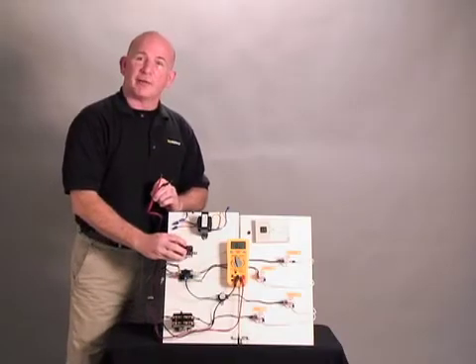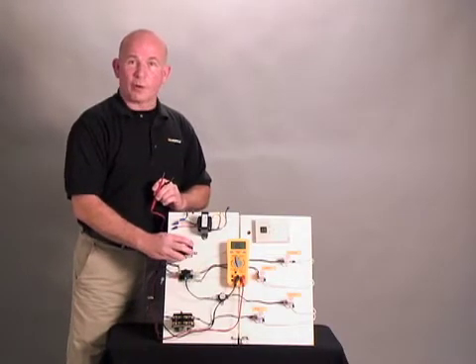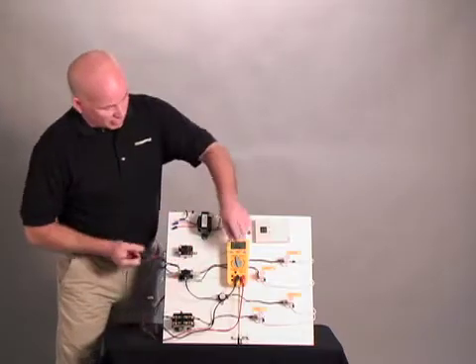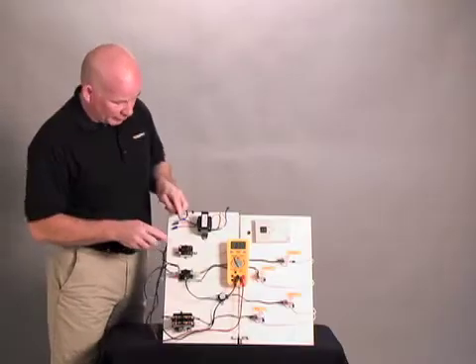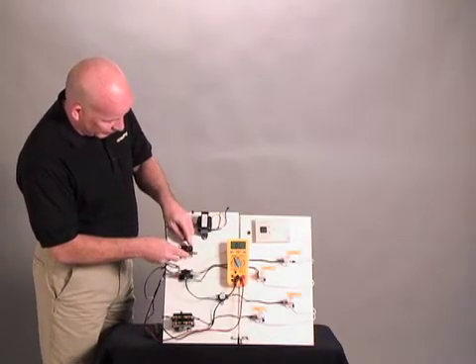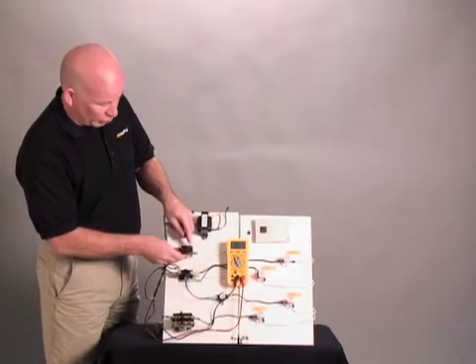Now between the other side, 5 and 6 should show closed. 2 and 4 should show open. So we will set to tone and then we will check. Closed and open. This is working correctly.